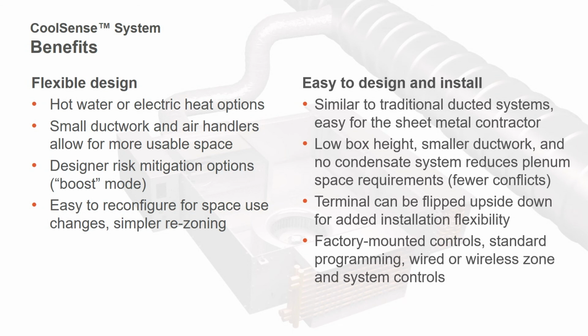installing the system. The low-height terminals, roughly 10.5 inches tall, along with smaller ductwork and no condensate drain system, require less plenum space and potentially higher ceilings. And because there is a drip pan on either side of the cooling coil, the terminal can easily be flipped upside down to resolve installation constraints.